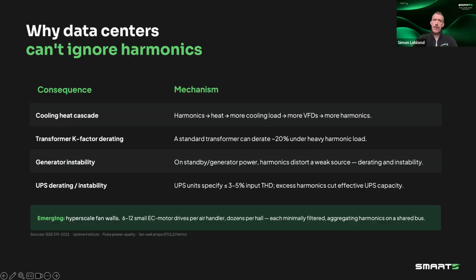Finally, we're seeing it more and more with EC motors, so electronically commutated motors, where they're creating fan walls with a lot of these EC motors. They're typically unfiltered, although we are starting to see some low harmonic EC motors. So they aggregate and they have a horrible harmonic signature, and really they're having quite an impact on the data center as well. So really, the headline here is that harmonics hit availability, not just efficiency for the data center.